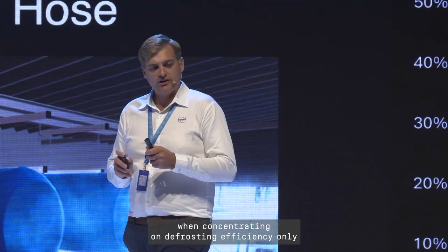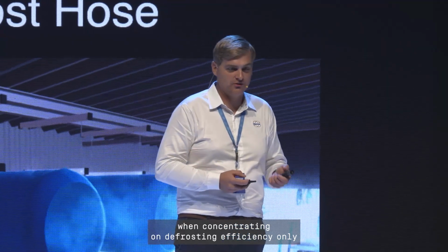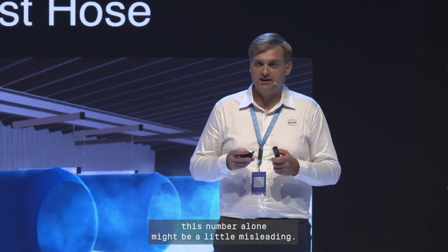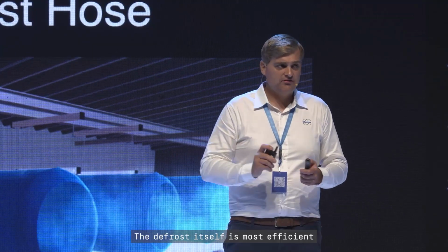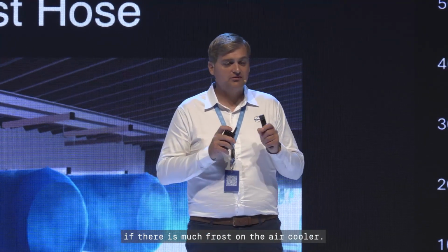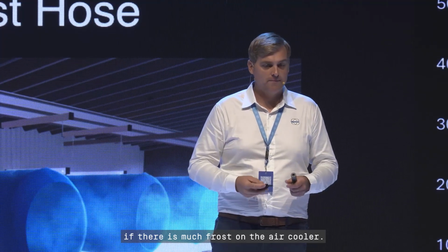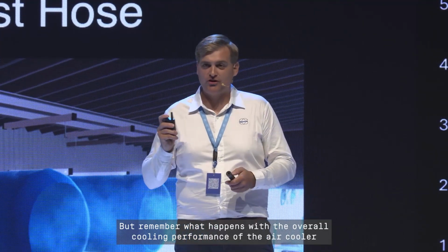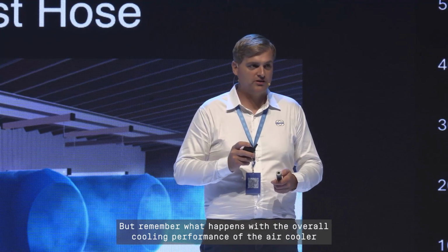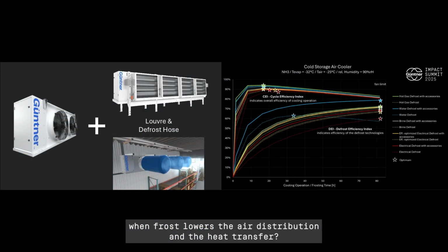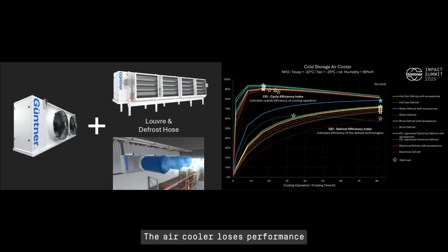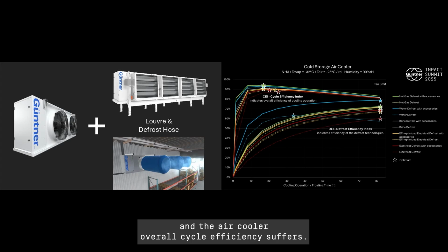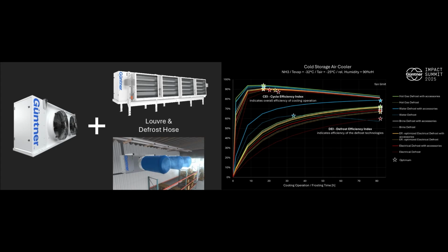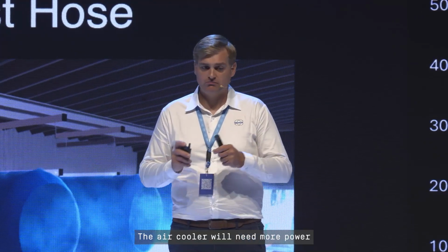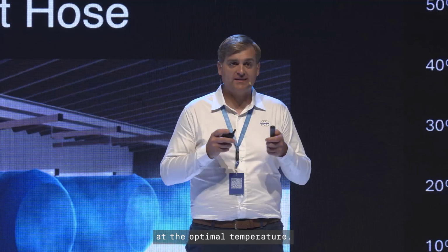This is because when concentrating on defrosting efficiency only, this number alone might be a little misleading. The defrost itself is most efficient if there is much frost on the air cooler. But remember what happens with the overall cooling performance of the air cooler when frost lowers the air distribution and the heat transfer. The air cooler loses performance and the air cooler overall cycle efficiency suffers. The air cooler will need more power to keeping the cold storage at the optimal temperature.